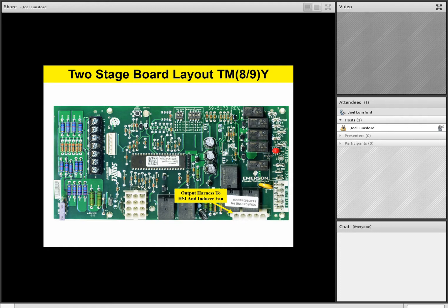We have a 12-pin harness with our 24 volt inputs and outputs, and again, this will be harnessed in from the factory, team. And remember, this is where your gas valve will be wired in. Your pressure switches and your safety circuits and so on will be wired into your 12-pin harness. Now you're going to notice, in the lower left-hand side of the board, a 3-amp fuse for protection. These come with a 3-amp fuse, but if you look closely at the silk screening, you'll see you can go up to a 5-amp maximum, but they come equipped from the factory with the 3-amp fuse.